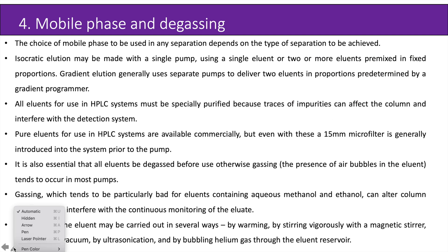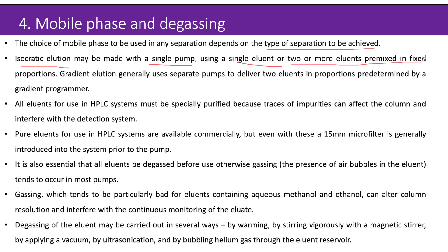Next is the mobile phase and degassing. The choice of mobile phase depends on the type of separation to be achieved. Isocratic elution may be made with a single pump using a single eluent or two or more eluents premixed in fixed proportions. Gradient elution generally uses separate pumps to deliver two eluents in proportions determined by a gradient programmer. All eluents for use in HPLC systems must be specially purified because traces of impurities can affect the column and interfere with the detection system. Even with commercially pure eluents, a 15 mm microfilter is generally introduced into the system prior to the pump.